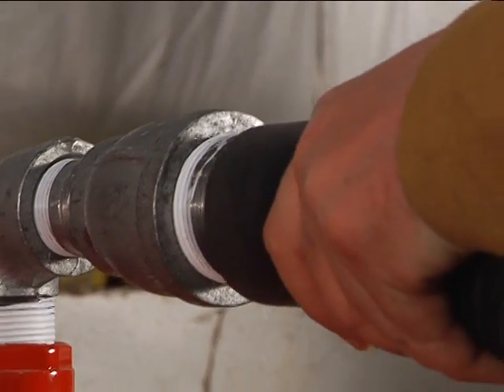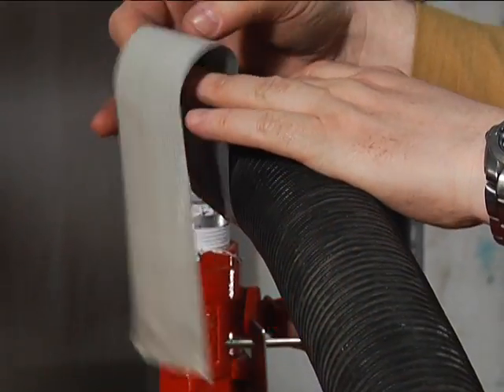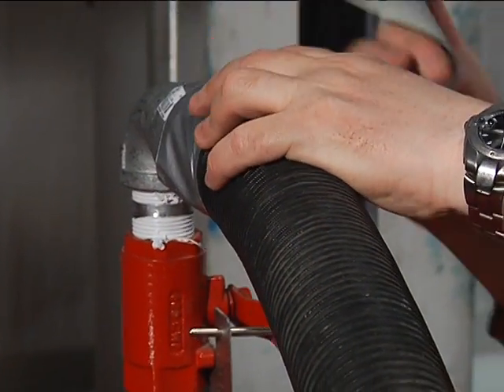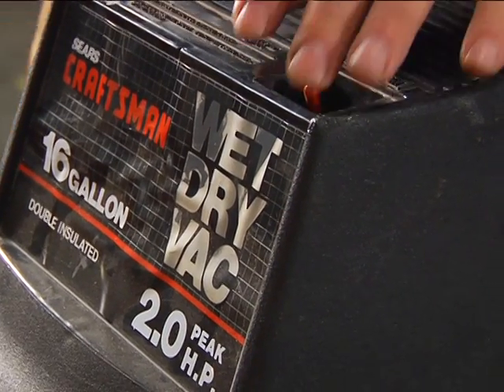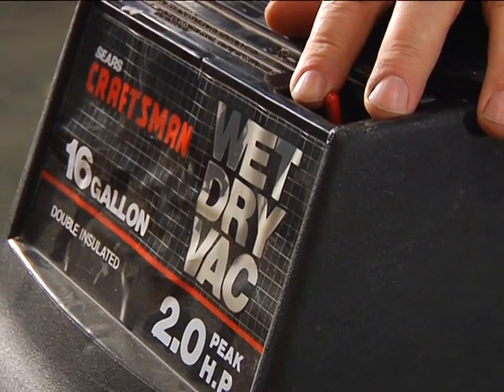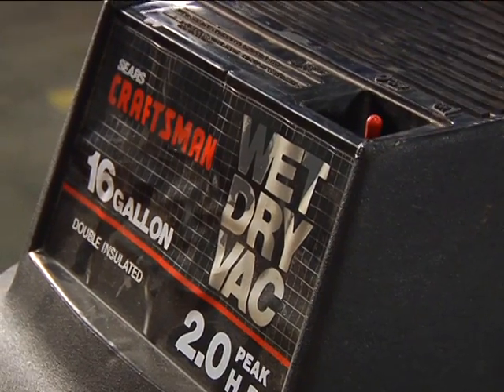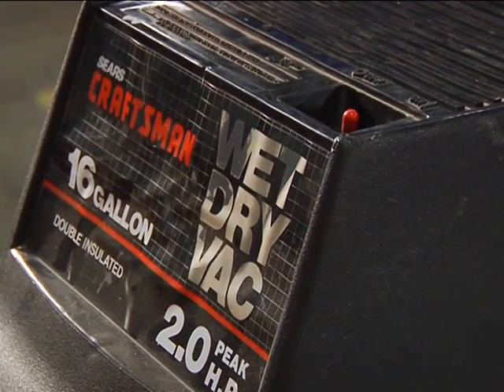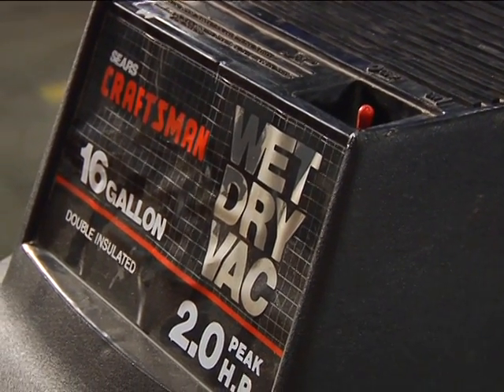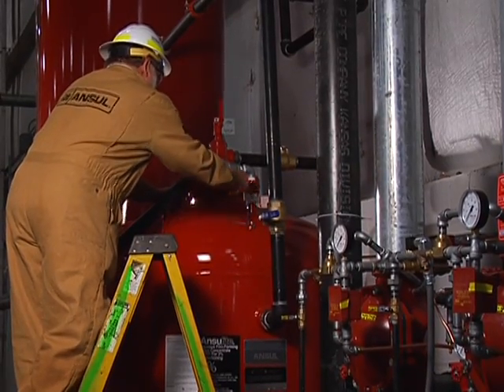Next, connect the vacuum hose to the tank shell vent valve by using pipe fittings and securing with duct tape. Now connect the vacuum hose to the shop vac and start the vacuum. Note the high-pitched sound from the vacuum before opening the valve. This will be the same pitch heard in the steps to come.